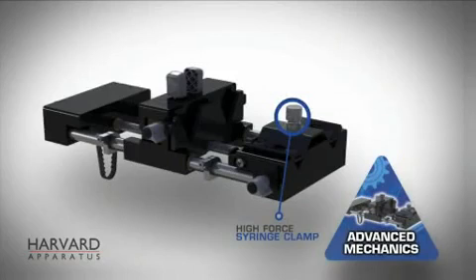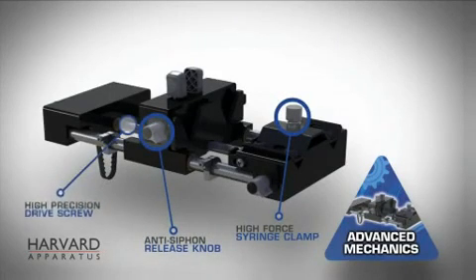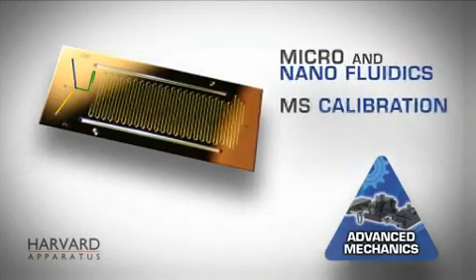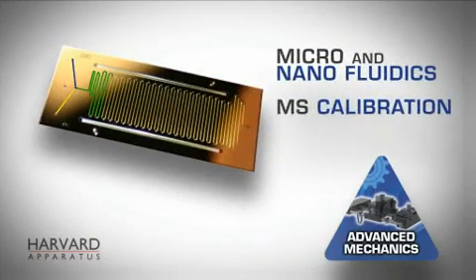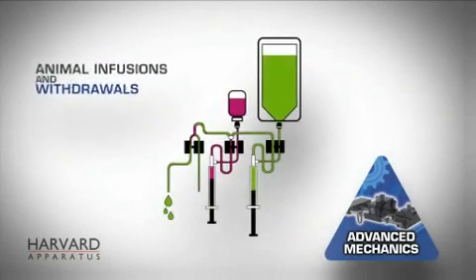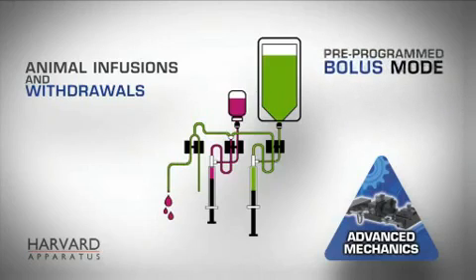The first PHD Ultra advantage is its new patented mechanical design for the highest performance flow of any syringe pump, allowing maximum smoothness and accuracy across the broadest flow ranges, from picoliter to hundreds of milliliters per minute at 75 pounds of force, making it the ideal solution for micro and nanofluidics and MS calibration. For animal infusions and withdrawals, the Ultra offers a pre-programmed bolus mode.